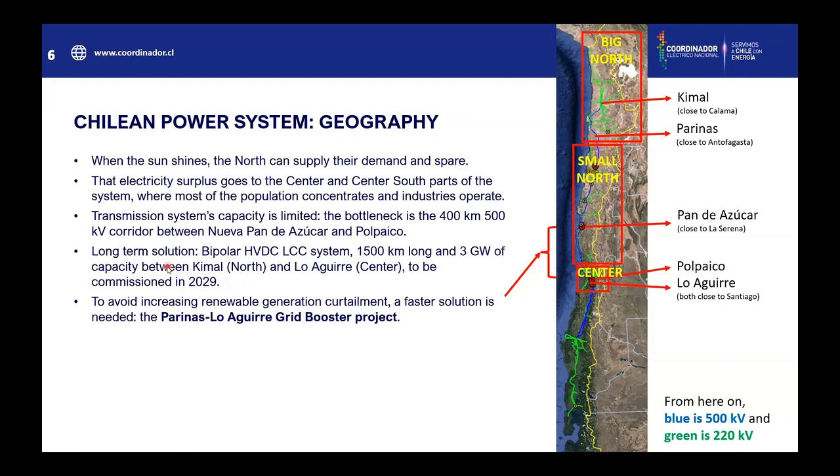The long-term solution is the bipolar HVDC LCC system between Kimal and Lo Aguirre. Kimal is in the big north and Lo Aguirre is in the center. That system is 1,500 km long and has a capacity of 3 GW, and it's expected to be commissioned in 2029. So in the meantime, to avoid increasing renewable generation curtailment, a faster solution is needed — that's why the Parinas-Lo Aguirre Grid Booster project was needed.